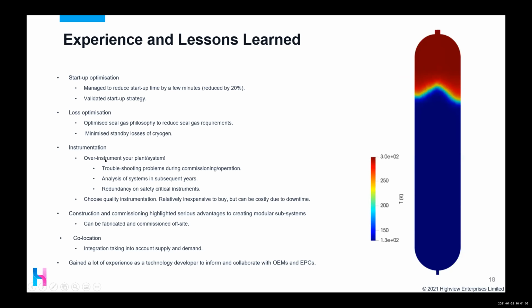On instrumentation, the key takeaway is to over-instrument your plant or system. Some of this is obvious. When troubleshooting problems during commissioning and operation, you will 100% regret not putting a flow meter or temperature sensor somewhere, because maybe you were only looking at what's necessary for the basic process system or safety systems. It's definitely worth over-instrumenting your plant, which will save you a lot of time during commissioning and operation.